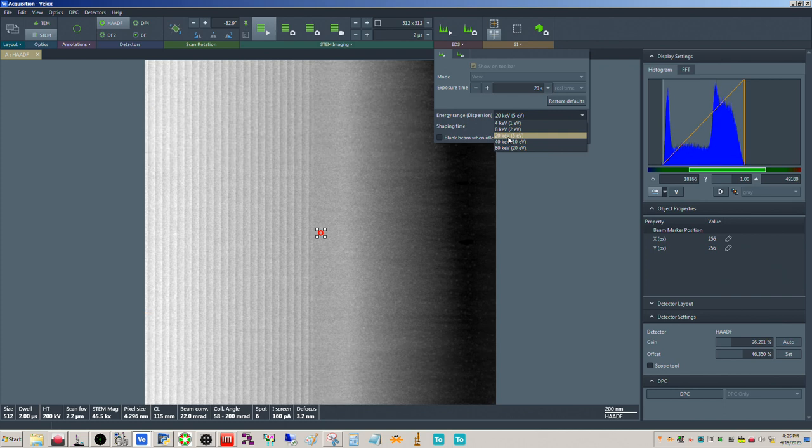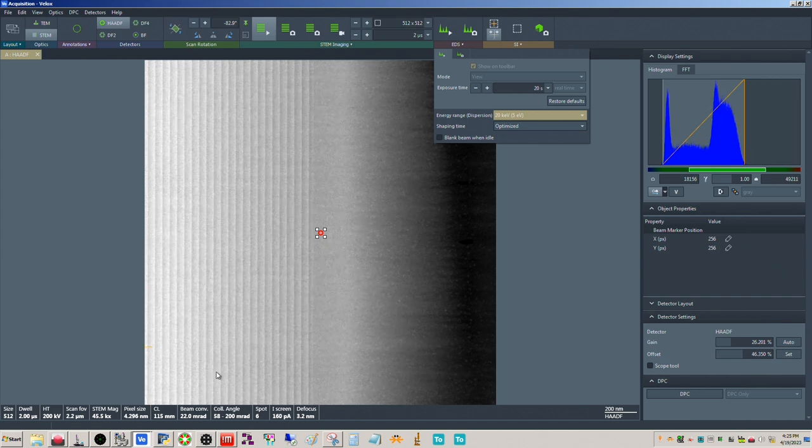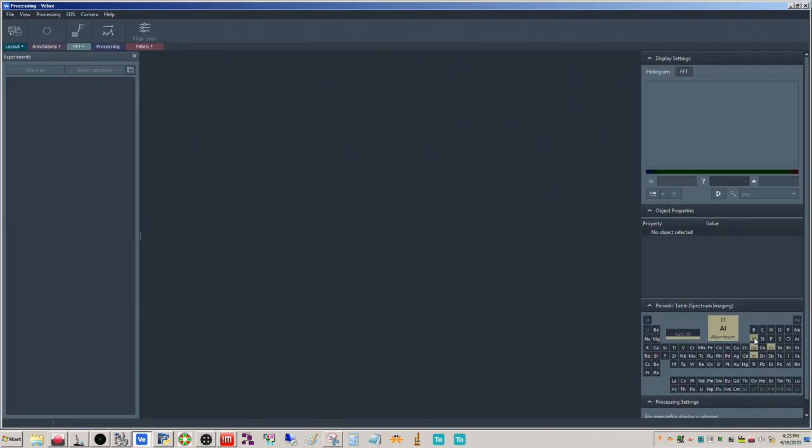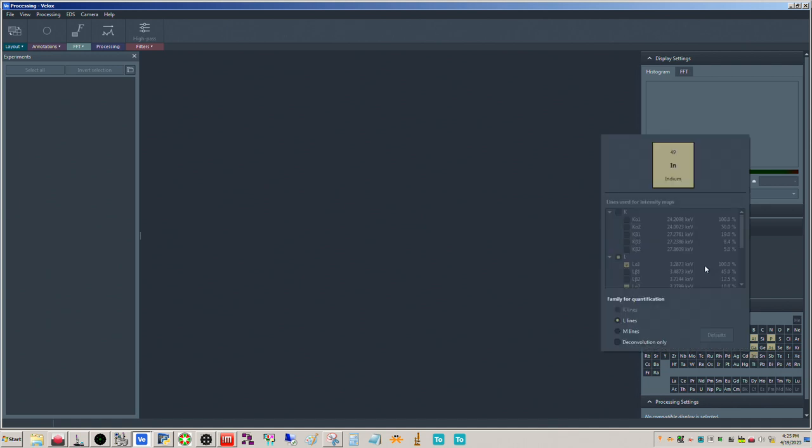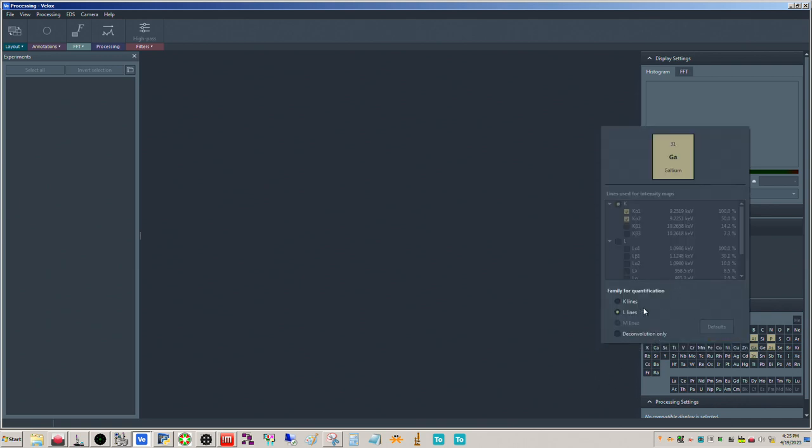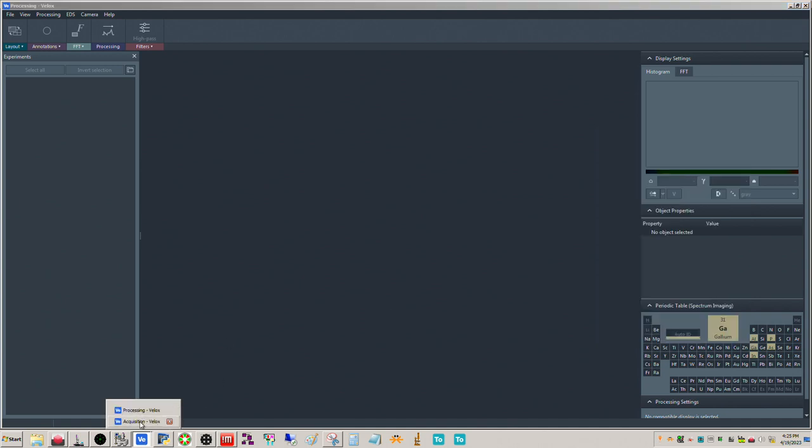But if you know what x-rays you're going to be looking for, right, so the elements we're going to be looking for here are, if we go to the processing window, basically all the ones I have highlighted here, okay? So indium's going to make the highest energy ones. If we right click on this, and we can't detect the K, so it looks like the L, I mean the L is in the 3 range. If we look at gallium arsenide, so this could be detectable. But actually, okay, in this case we could use the K or the L. Usually the highest energy x-rays that can be detected is the way to go.